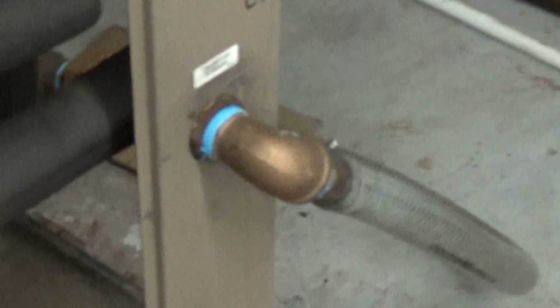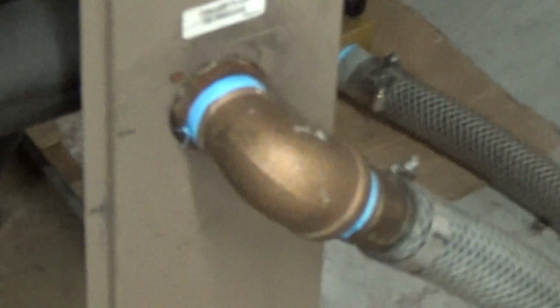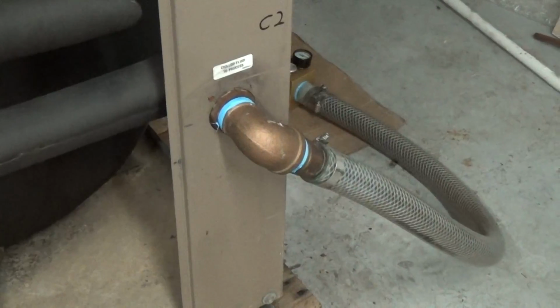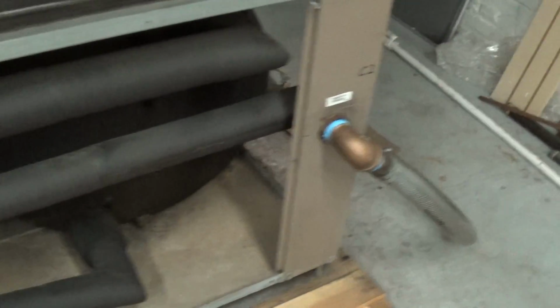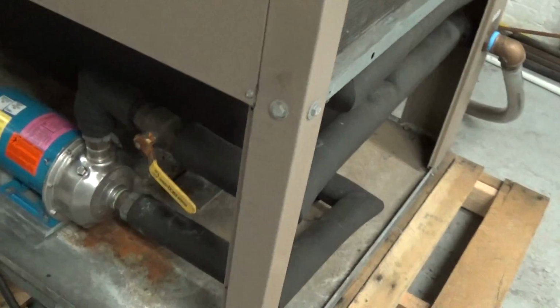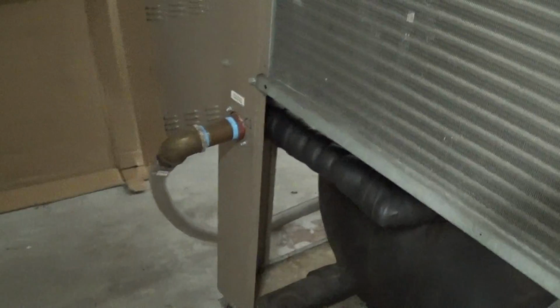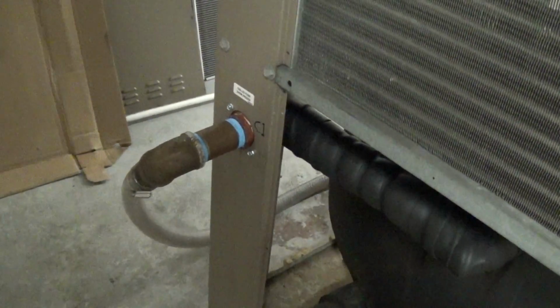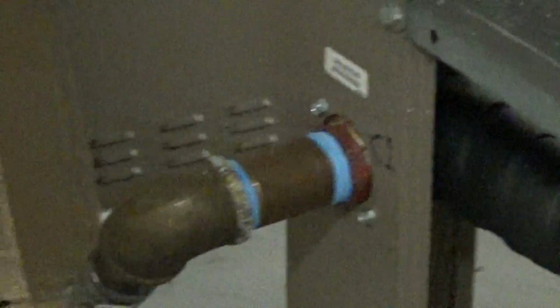You have going out to your process, you have this shut off here already, so it's up to you. You really don't have to put another shut off there unless you want to. You can. It'll avoid you from having to go inside the covers here if you ever want to do some maintenance on your system. But I would put in your process piping, the fluid coming in, I would put a shut off there.